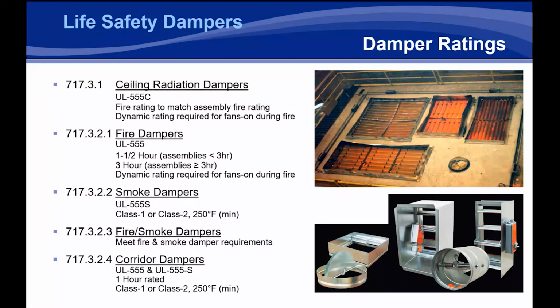The only thing that may be open to design engineers and contractors is making sure the air handler that's supplying the unit shuts off, as if they're using a static assembly and a static damper, which is much more cost effective, they may need to shut that system down, whether with a smoke detector or some type of thermostat. Another addition in the 2015 version of the code that still confuses some regions is the language addition of corridor type dampers. These are really tunnel type corridors, and I've got some slides explaining that. When we get to the corridor section of this presentation, I'll go over that in more detail, as it may have some details that architects may use incorrectly that may cause problems when you're going through your final certification and inspection to get your certificate of occupancy.